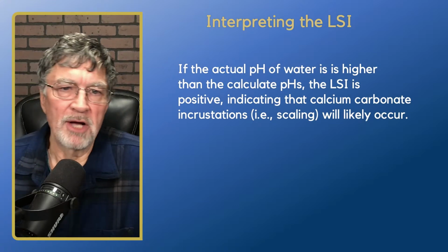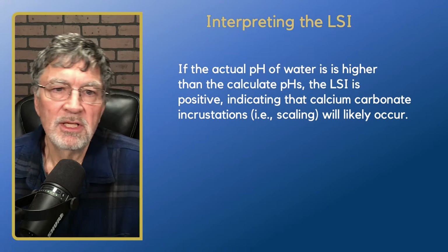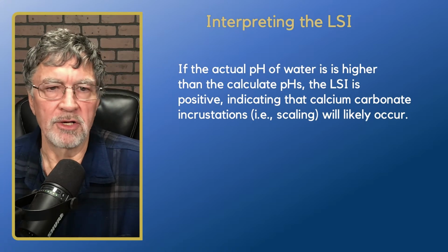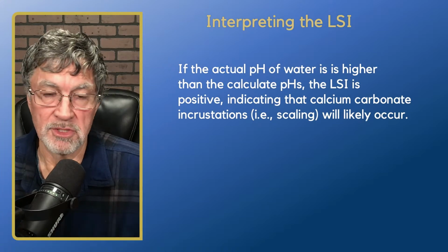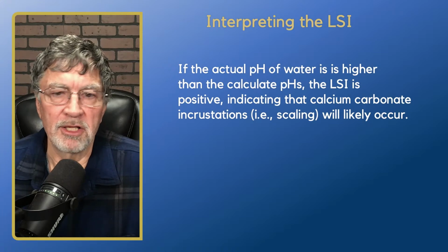So if you have a positive LSI for a long time, you're probably going to get calcium carbonate plugging going on in your well, with the development of the mineral incrustations that are going to plug up your screen. So that can help you in planning your well rehabilitation.